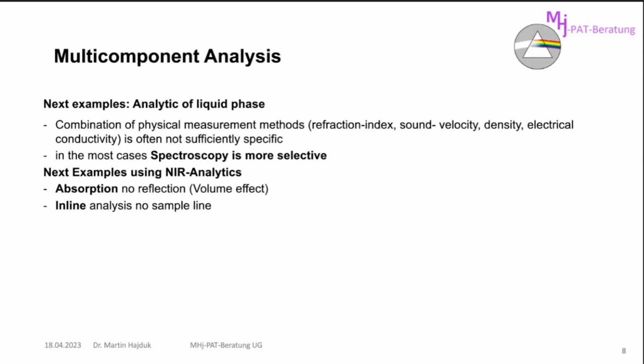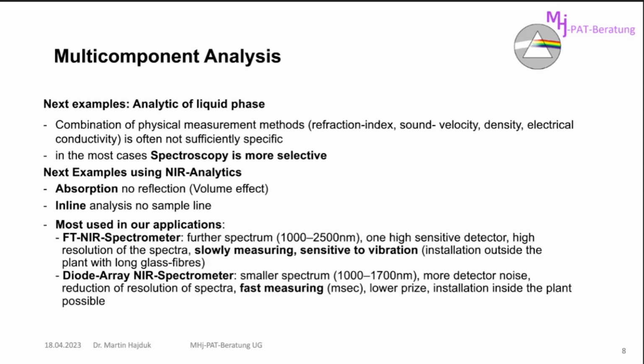I want to have an absorption sample, so I can get a volume effect. And if possible, inline analysis. So in most of our applications, we can use 2 different spectrometers. That can be the FT-NIR spectrometer. We have a full spectrum from 1,000 to 2,500 nanometers. That means 10,000 to 4,000 wave numbers. And we have one highly sensitive detector with low noise, also a high resolution of the spectrum. But the measurement is slow and sensitive to vibration. So normally we have to install the NIR spectrometer not inside the plant but outside the plant, and then we have a long glass fiber connection to our sample point.